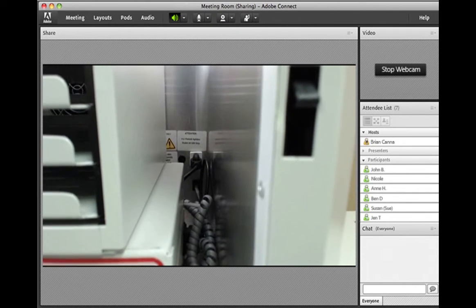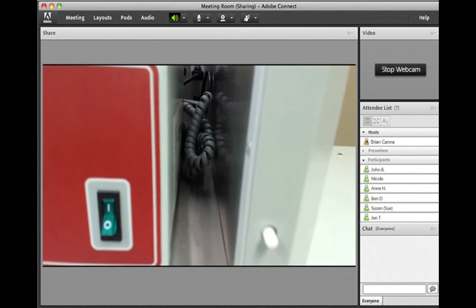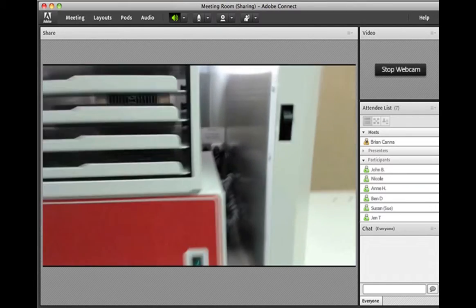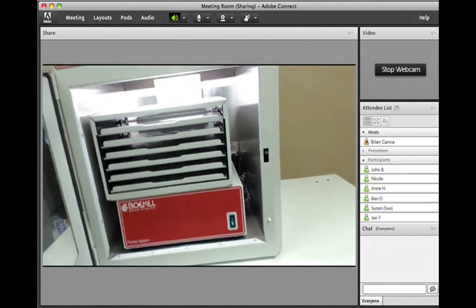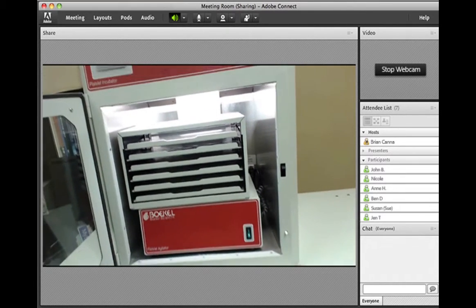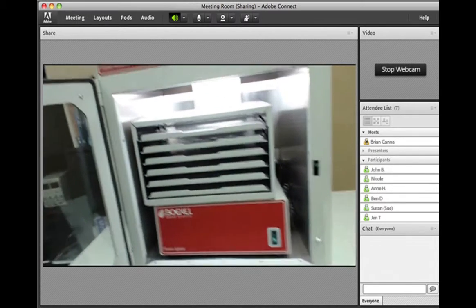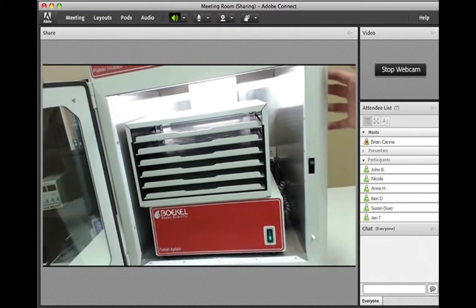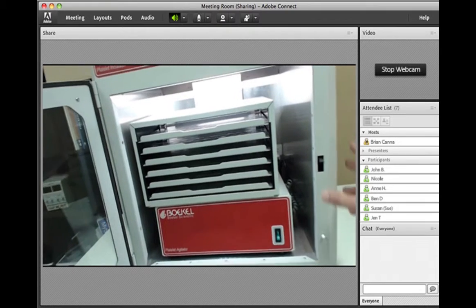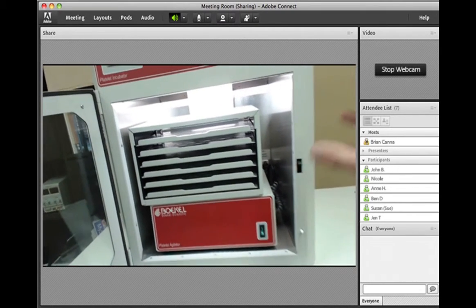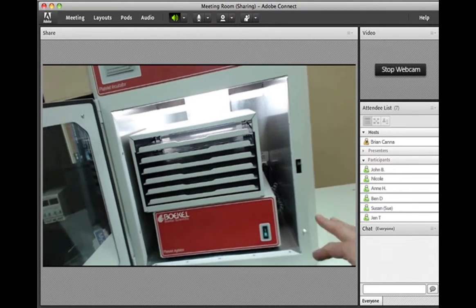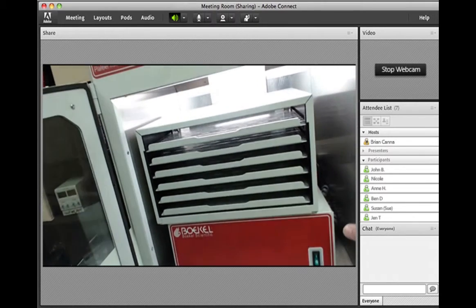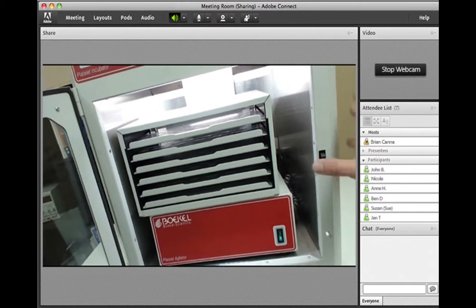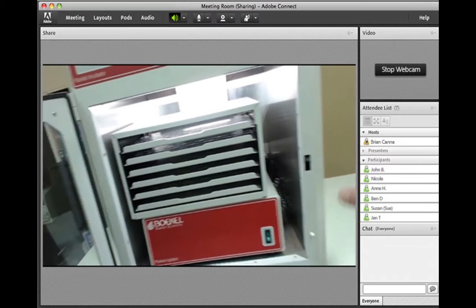In the back of the unit we have our power connections and our communication to the agitator. If the agitator were to fail, say it turns off and it's supposed to be agitating, a signal would be sent to the control system and it would create an alarm. There's also a door alarm, so since this door is open right now it's okay, but if it were to stay open for an extended period of time, an alarm would occur, and maybe that'll happen while we're working with it.